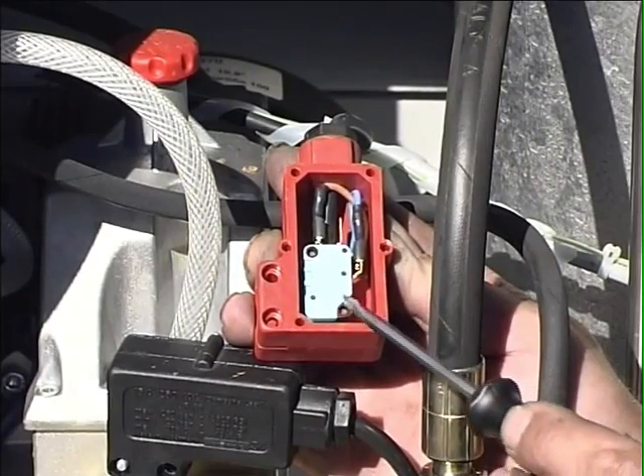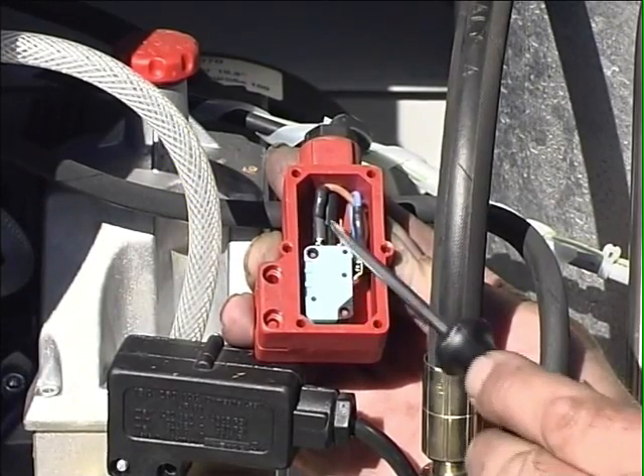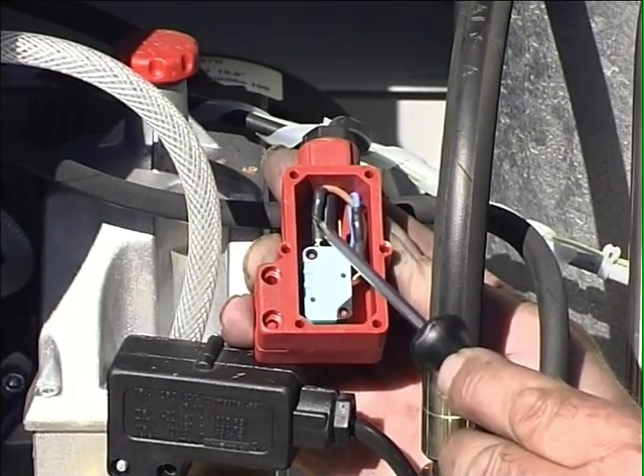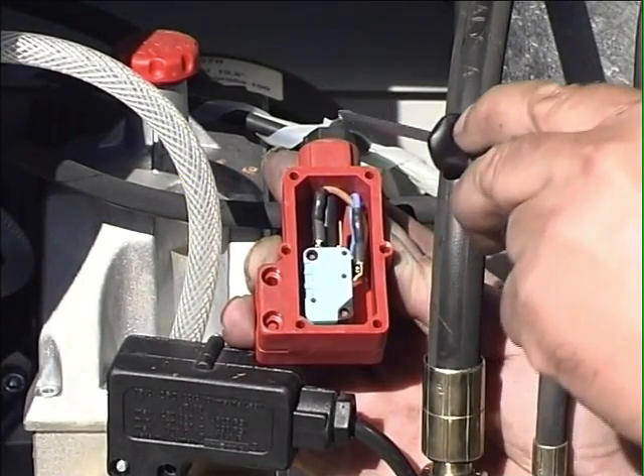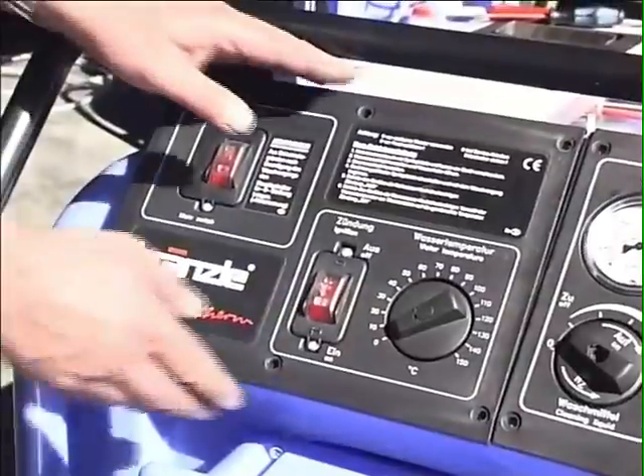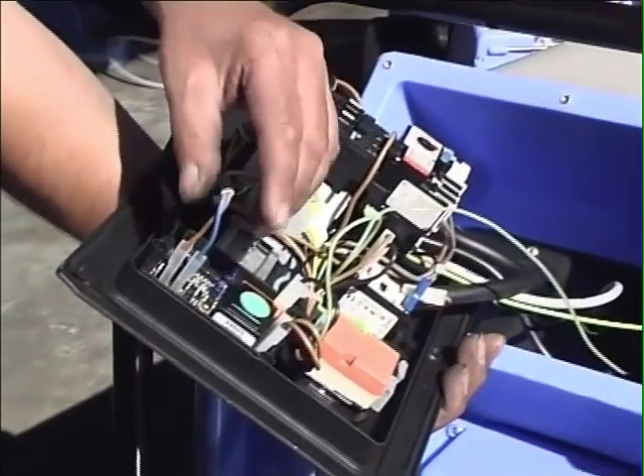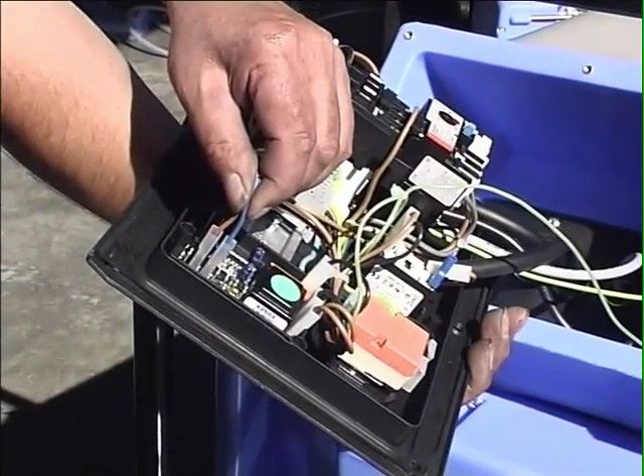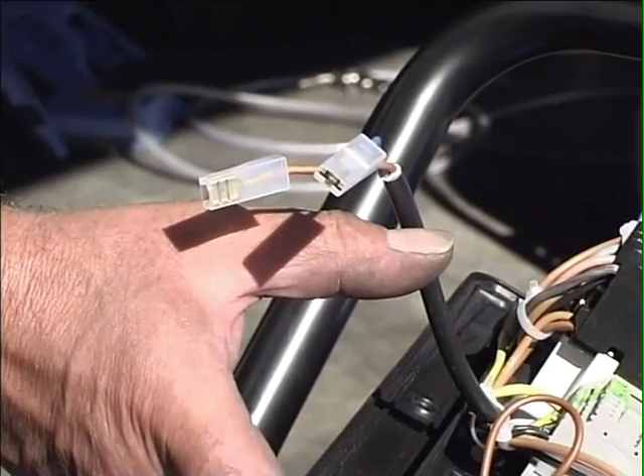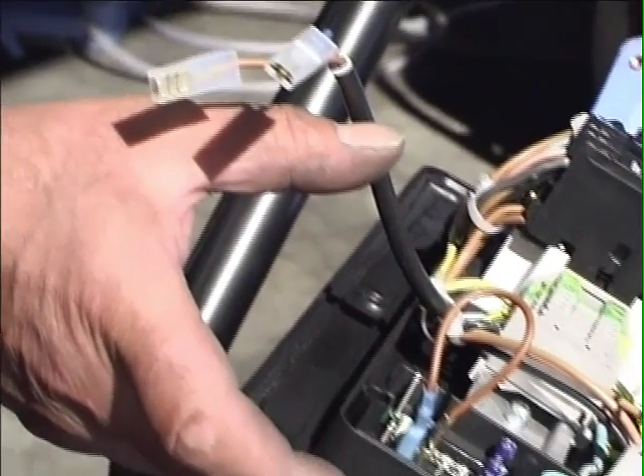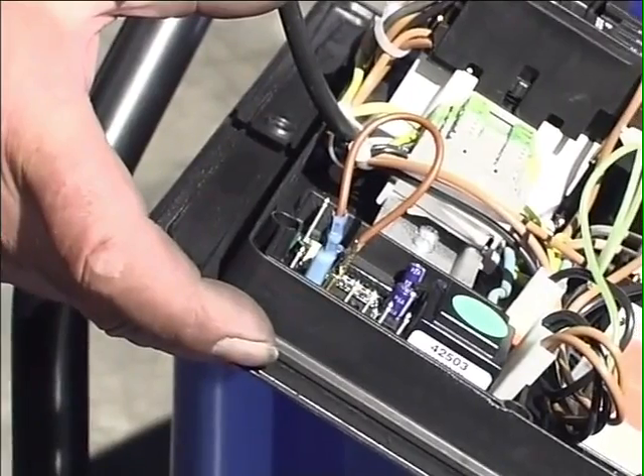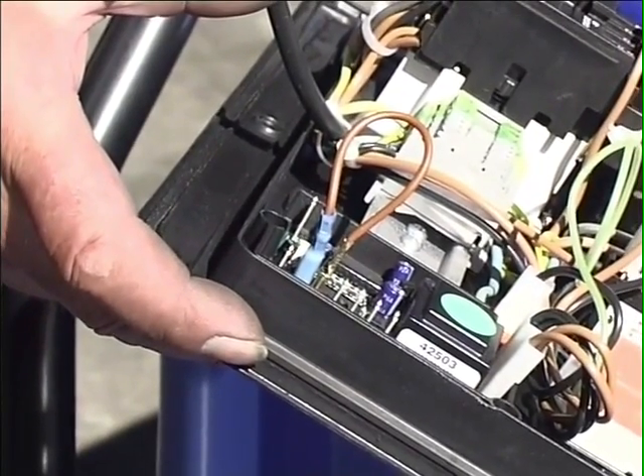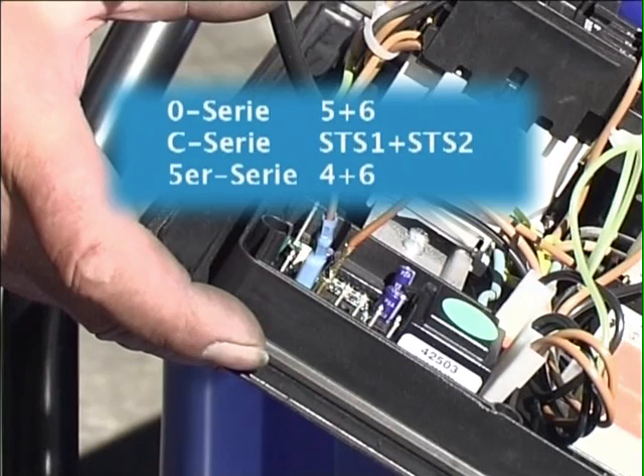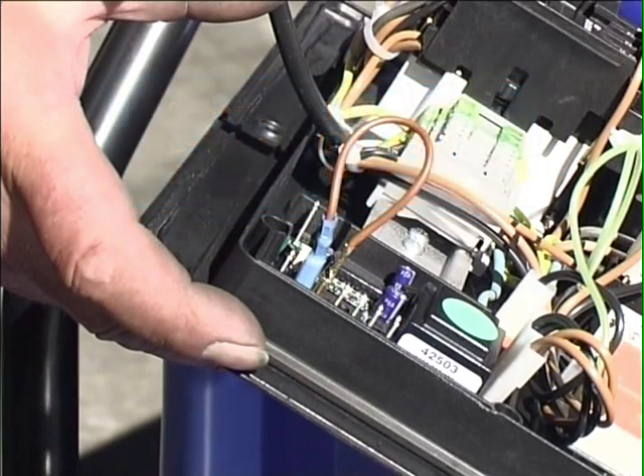Check micro switch, terminal and cable connectors. The problem may be related to the control circuit board. Check the cable connections and, if necessary, put a bridge between terminals 5 and 6 in the case of the O series. In the case of the S series, do this for terminals STS1 and STS2 and terminals 4 and 6 for the 5 series. If start-stop still does not work, the circuit board is defective and must be replaced.